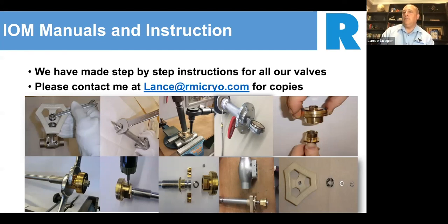I've got these on file. They are actually going out with every valve now, but unfortunately, if you have a tank and they've been installed, you do not have that IOM. Please contact me. Here's my information. This will show your service techs exactly how to open up the nuts, how to torque them. I have torque values on there, how to replace the seats. I even have some little tricks as well to get these things open and closed properly. So please feel free to reach out to me for any of these IOM manuals. I've got them readily available and they're fantastic. Molly, if you want to go to the next slide.